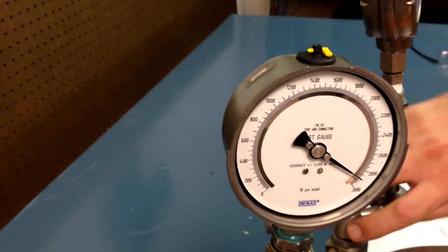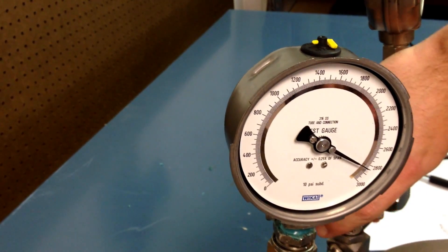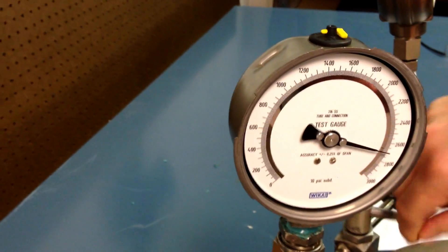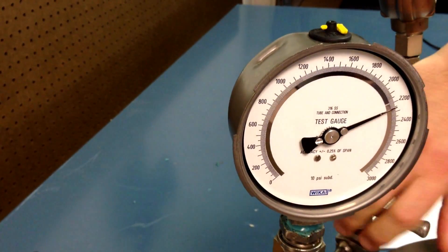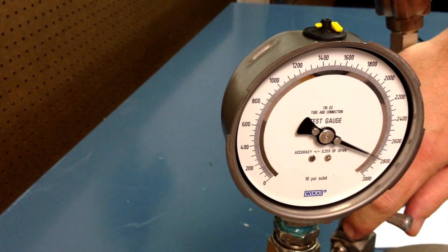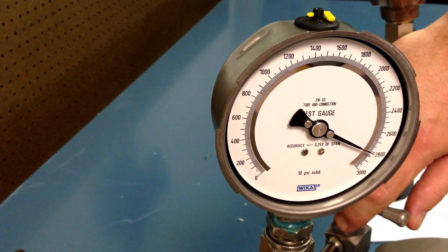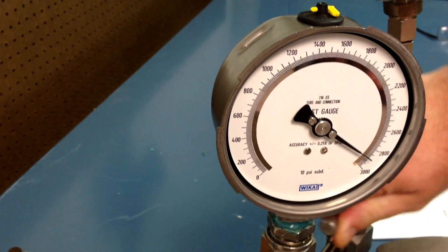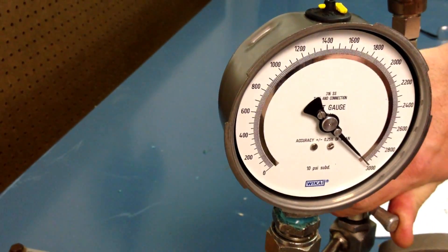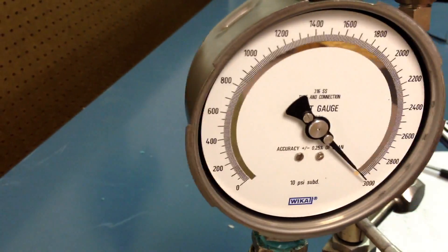Next point is 3000 PSI, full scale. Do my fine adjustment here. Which is right about there. 3000 PSI. I'm at 2952.